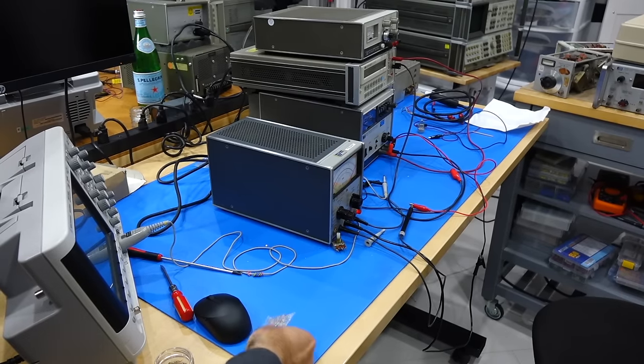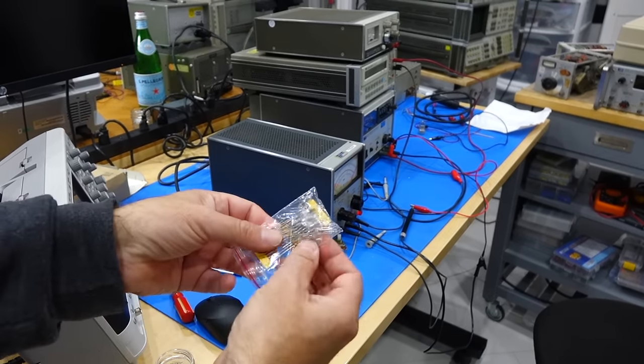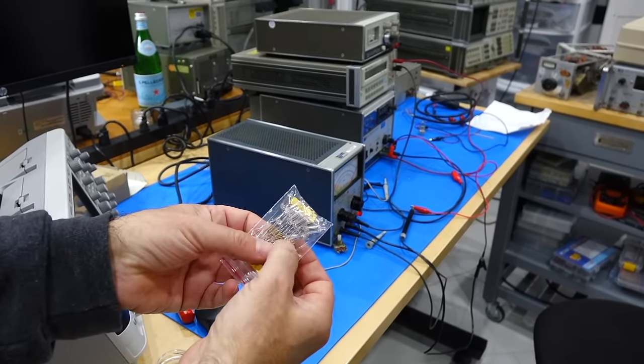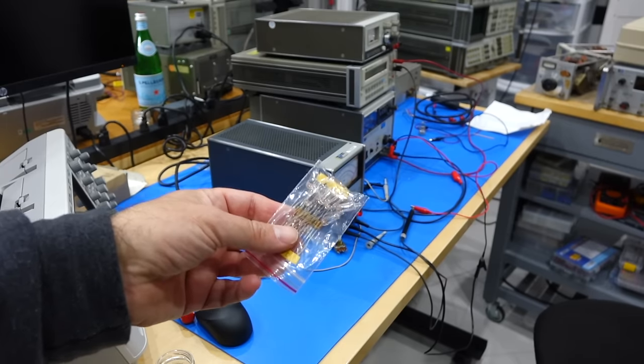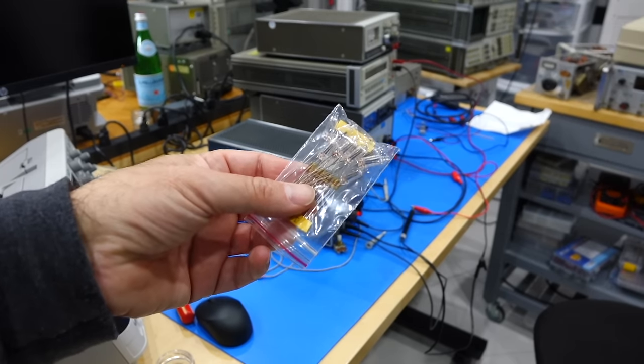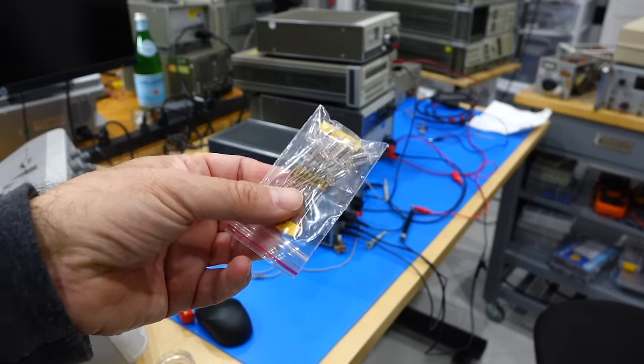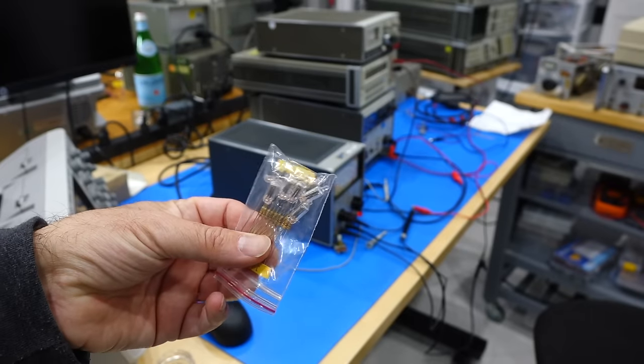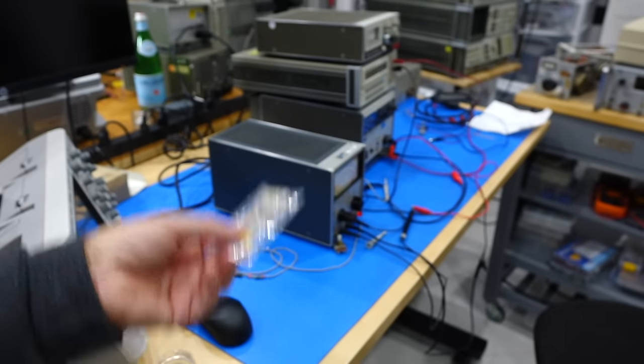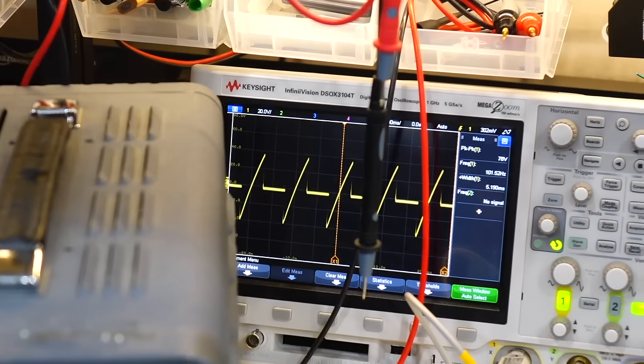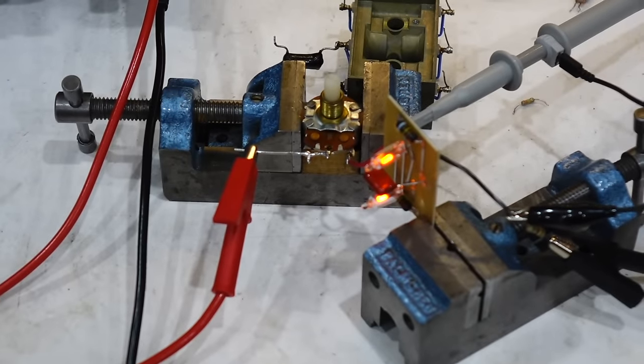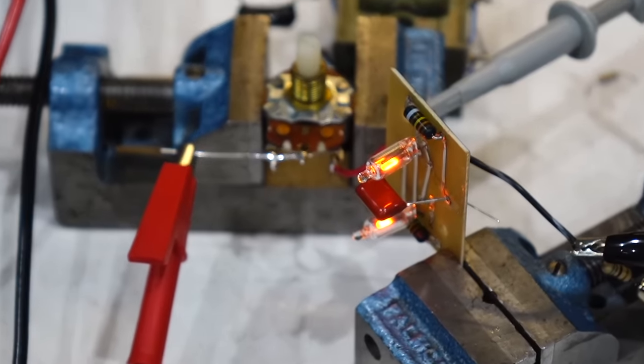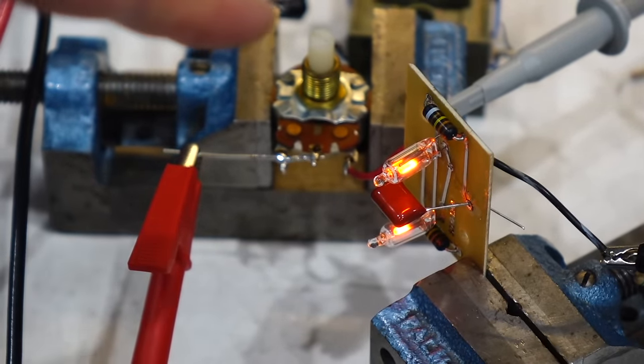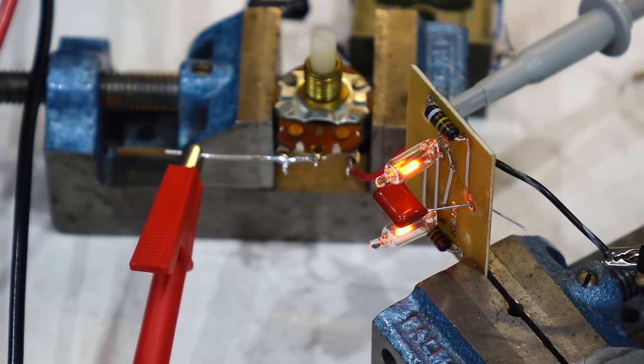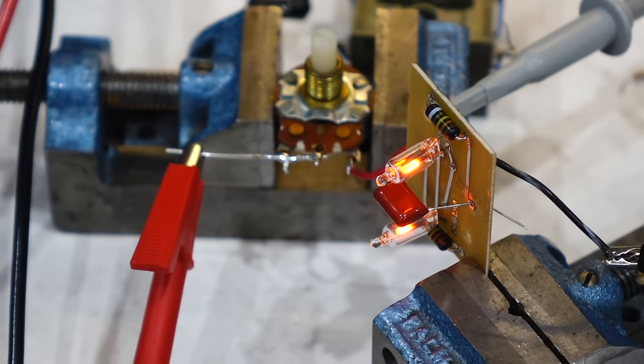So finally I got the correct neon lamps to go into the chopper, so those are the high brightness, high current, but somehow long life, 25,000 hours. So they should be closer to the original, so we need to go back in there. So we had to readjust the resistors and caps for our new neons once again, which is no different than what they did at the factory back then. Caps and resistors were hand-selected to match the pair of neon tubes in each photosensor.